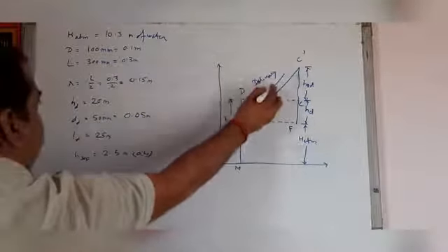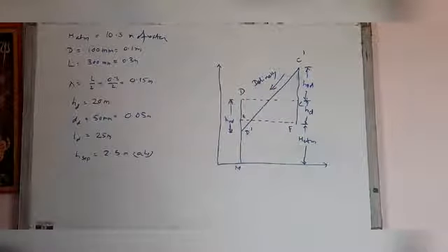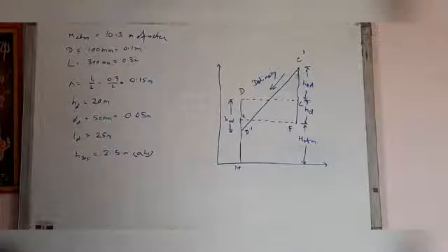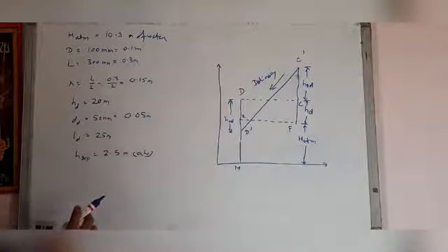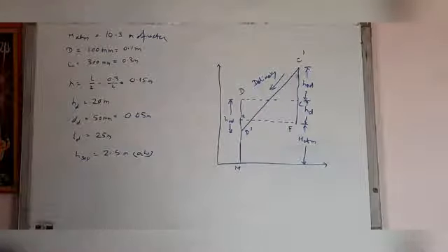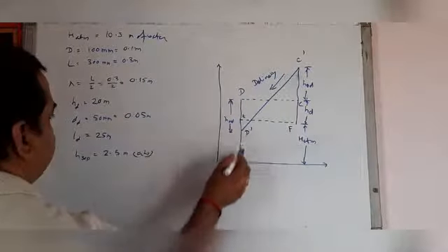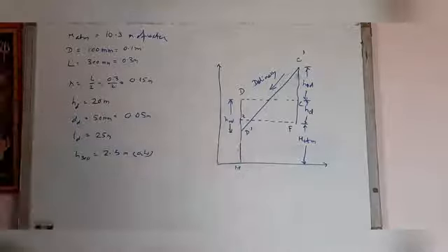The absolute pressure head during the delivery stroke is minimum at the end of the stroke only. It means if separation is to take place, it will occur only at the end of the delivery stroke, where the pressure head will be equal to the separation pressure head. The absolute pressure head at the end of the delivery stroke from this figure is equal to D dash M.